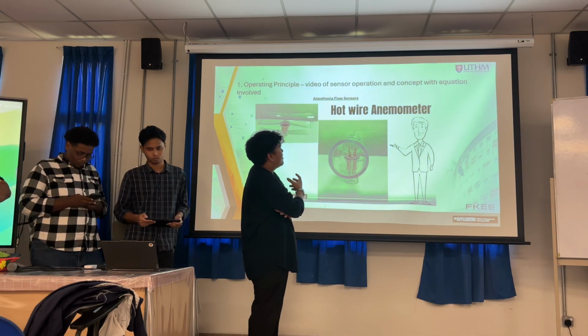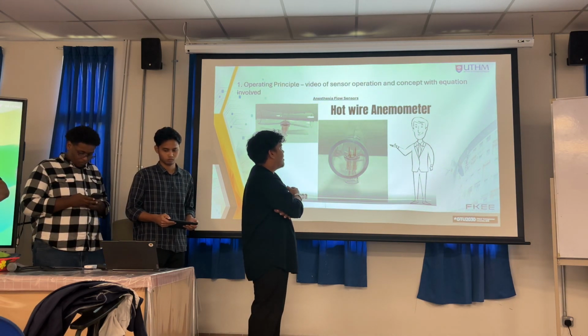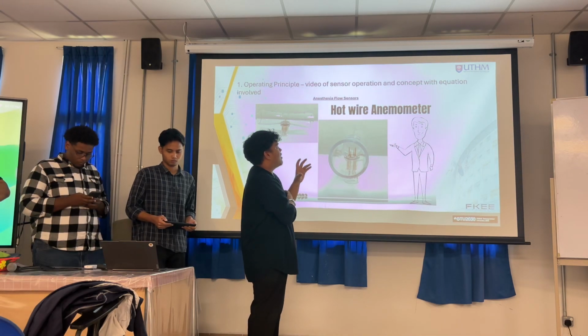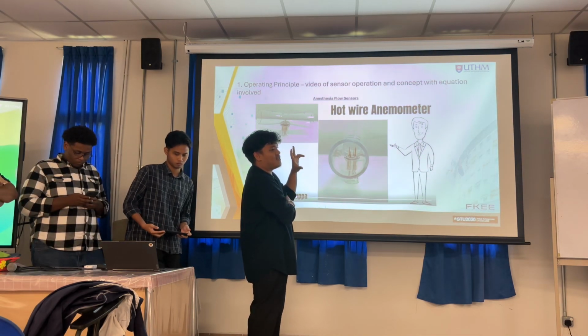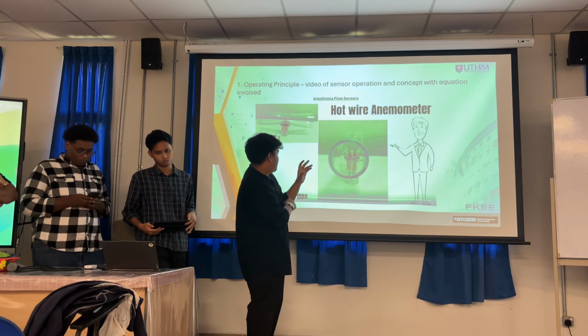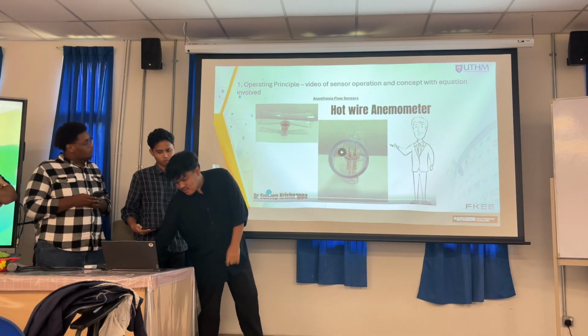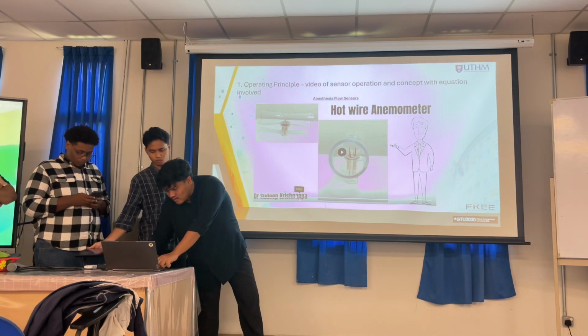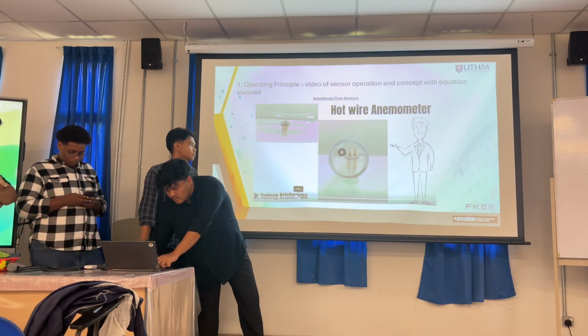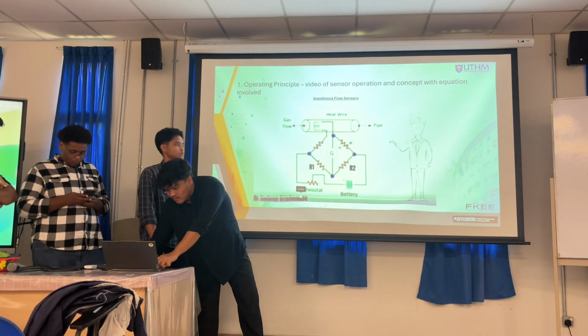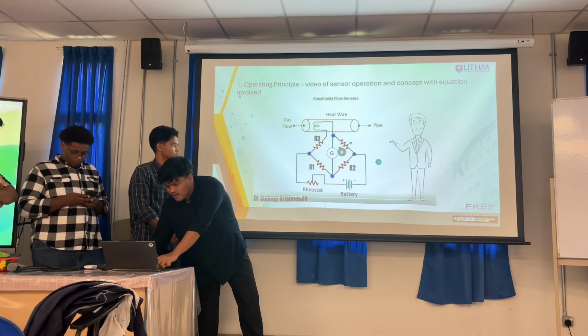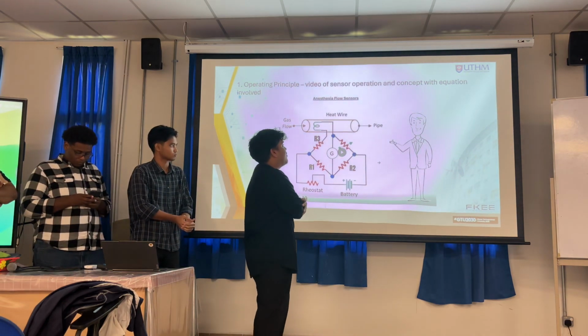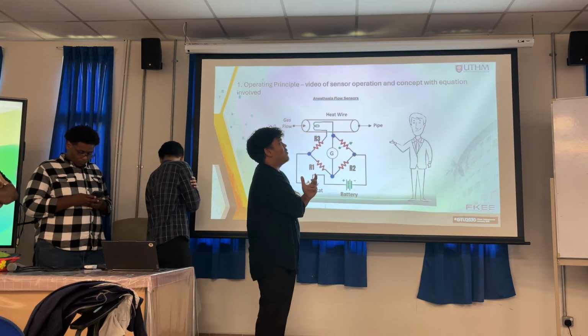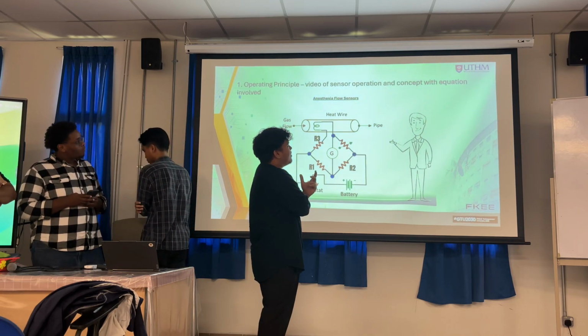The flow sensor uses a hot wire anemometer in the anesthesia machine at the hospital. This sensor uses the amount of flow for pressure monitoring.